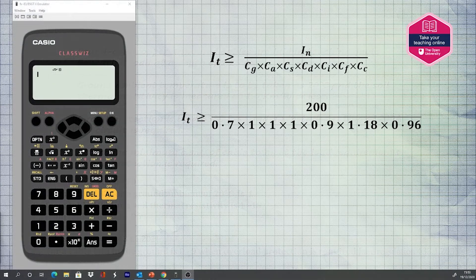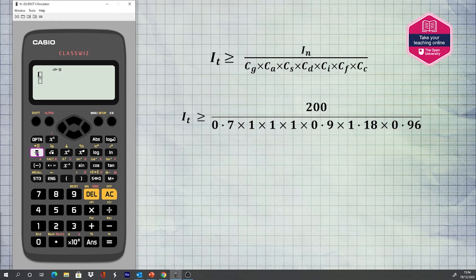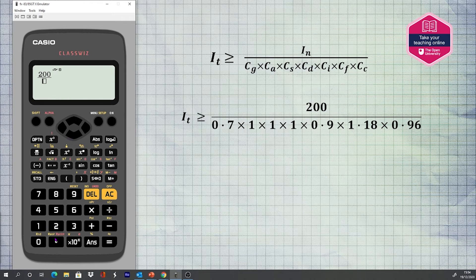The formula shown is to calculate the tabulated current IT, which is used to decide which cable to use in this example. The formula includes all the factors. Where a factor is not applicable, one is used. In practice, only the factors different to one are used.